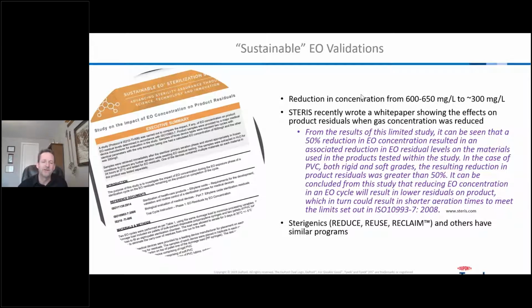So really what this involves is reducing the gas concentration. Historically, when I was doing EO validations for 25 years, we would always recommend around 600 to 650 milligrams per liter. That's being cut in half now. People are looking at going all the way down to 300 milligrams per liter. Steris did a white paper showing that when they reduced the concentration, the residuals on the product were also reduced, in some cases by greater than 50%. So there's a big benefit there.